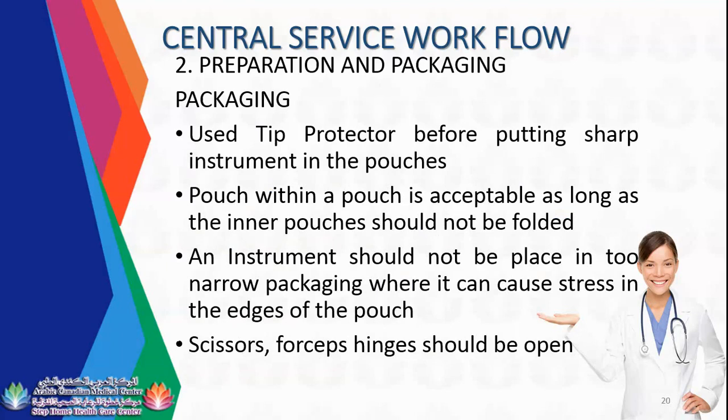once you are putting an instrument or sharp instrument in the pouches, you need to use a tip protector. A tip protector is actually a silicone rubber that you can put on the tip of the sharp object so that it will not penetrate the pouch. If you don't have a tip protector, then you can double pouch the instruments. A pouch within a pouch is acceptable, yes, as long as the inner pouch is not folded. So you need to make a smaller pouch inside and a bigger pouch outside.